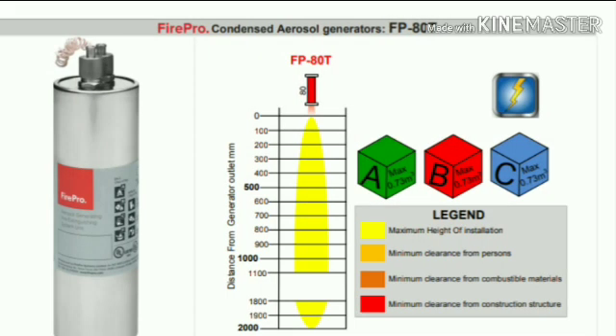Next generator is FP-80T. Activation line supervision current maximum: 5 mA. Aerosol discharge time: minimum 5 seconds, maximum 10 seconds. Number of discharge outlets is 1. Generator dimensions: height 185 mm, diameter 51 mm. Self-activation temperature of FPC: 300 degrees. Class of fire: NFA 2010 ABC. Generator coverage constraints: minimum height 0.45 m, maximum area 2.12 m², maximum throw 2.34 m. Maximum height of installation: 2 meters. Minimum clearance from person: not required. From combustible materials: not required. From generator casing: 6.4 mm.